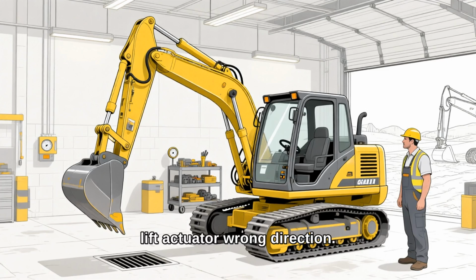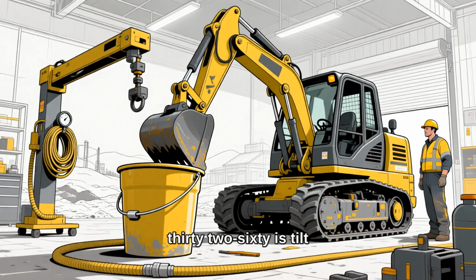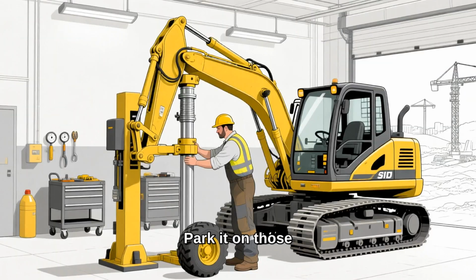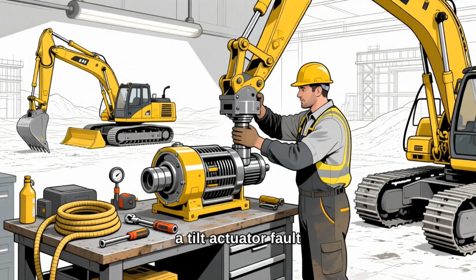3259 is lift actuator wrong direction. Read that twice. It moved away, nobody asked it to. 3260 is tilt actuator wrong direction. That's not a performance complaint anymore. That's control integrity. Park it on those two. A control that answers wrong is worse than a control that won't answer. 3231 is a tilt actuator fault outright, and now you're pricing a part instead of cleaning a connector.